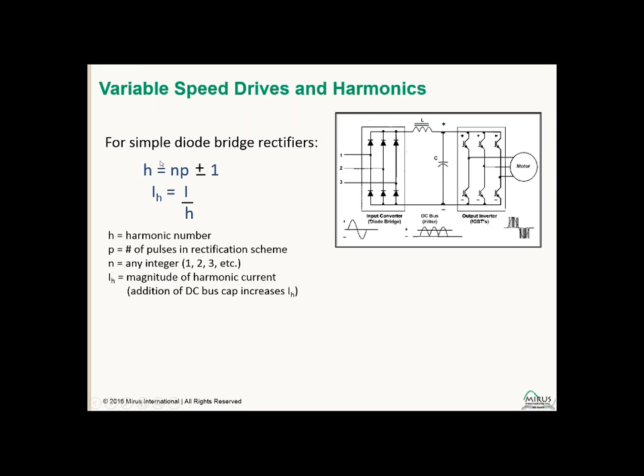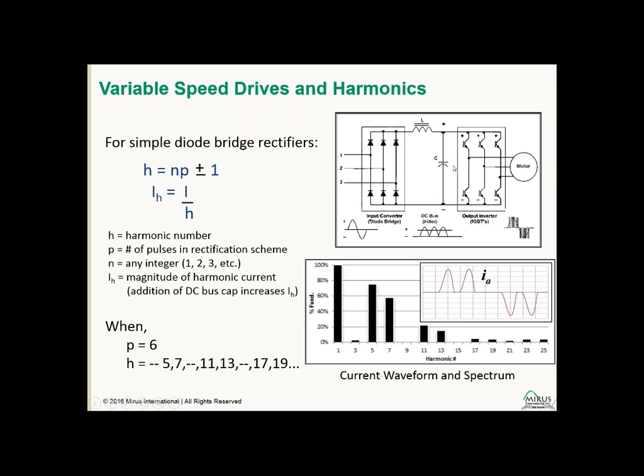In this application, the harmonics that are present will typically follow this relationship: NP plus or minus 1, where N is any integer and P is the pulse number of the rectifier. And the harmonics that are present are typically inversely proportional to the harmonic number. So the higher the harmonic number, normally the lower the magnitude of that harmonic, if it's present. So when we have a 6-pulse rectifier, as shown here, we substitute P equals 6. When N equals 1, we have 6 plus or minus 1, so we have 5th and 7th harmonics. When N equals 2, we have 2 times 6, which is 12, plus or minus 1, so we get 11th and 13th, and so on. So the predominant harmonics we're going to see are 5th and 7th, 11th and 13th and so on. And the input current waveform is basically a double-humped, pulsed current waveform, with 2 humps on the positive and 2 humps on the negative side.